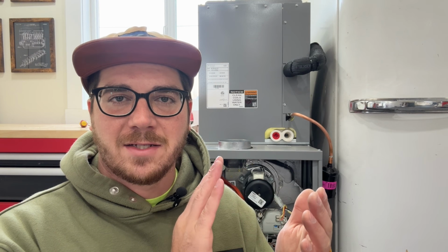Well guys, those are the 5 things that I recommend checking on your gas furnace if it's not working. Obviously there's many other things that it could be, but overall a gas furnace is pretty basic. There's not a ton of stuff unless you have a really sophisticated one, but you really should go to that code plate and see what code it's showing, and that will kind of narrow it down for you.